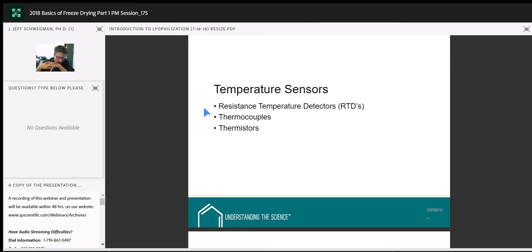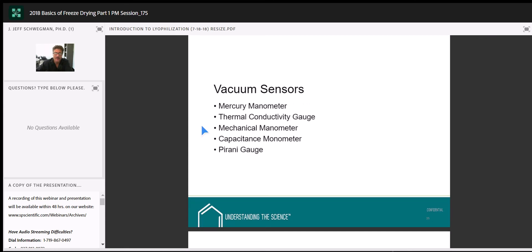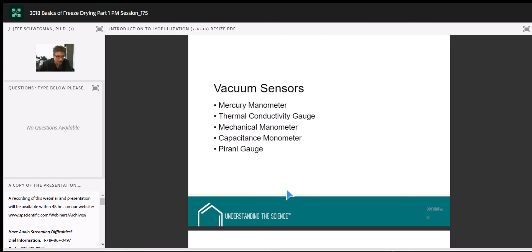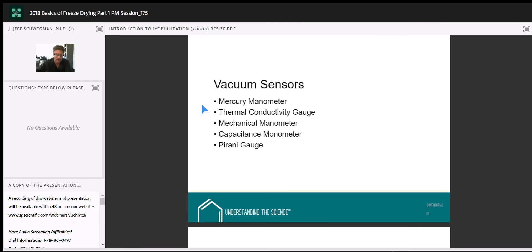Resistance temperature detectors (RTDs): basically a platinum wire — we put a current across it, and as we change the temperature of that wire, the resistance to current flow changes, which we correlate back to temperature. A typical RTD has a platinum wire wrapped around a ceramic core and covered in glass. Advantages: accurate, very repeatable, stable through a very high temperature range, high output, inexpensive, and available in many configurations. Disadvantages: they are self-heating — they'll warm their environment slightly. Also, the temperature result is an average over the entire length of the sensor, so they cannot do point sensing.